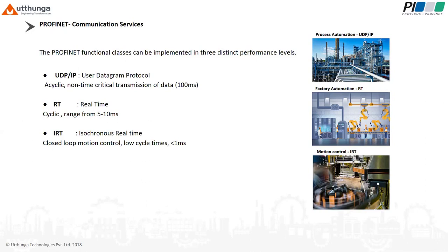And then comes isochronous real-time. Some applications like closed loop motion control require not just low cycle times, they also require specific behavior from the network. The data should be strictly sequenced and should never be vulnerable to collision or jitter. Jitter is nothing but a delay in the packet from the devices to the controller. Isochronous real-time networks can operate with cycle times as low as 31.25 microseconds. That is 32,000 samples per second. As we say, it is below 1 millisecond.